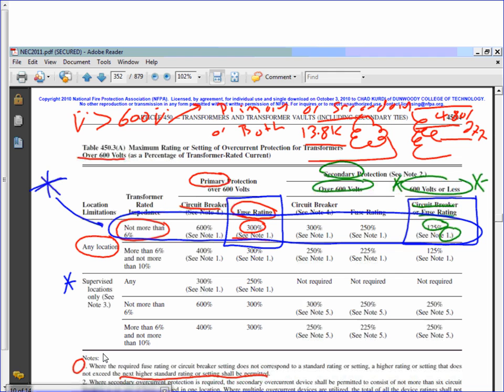Your default is any location. So you have primary protection and secondary protection. If the primary, then you have to go fuse and circuit breaker. The first row is the impedance 6 or less, not more than 6. That's your default. If you're circuit breaker, you go 600. If it's fuse, you go 300.